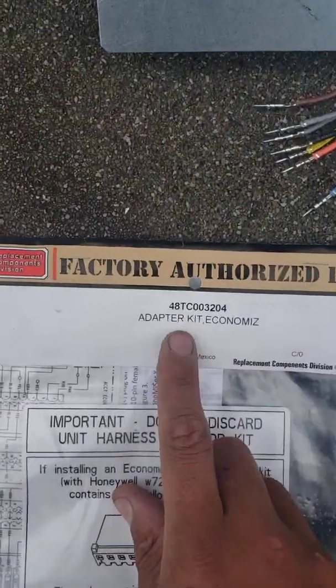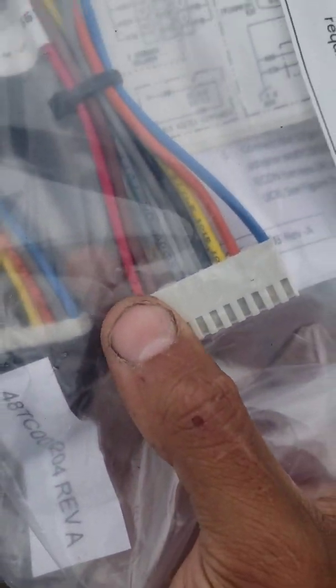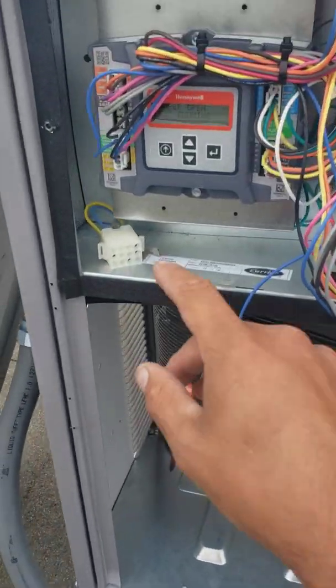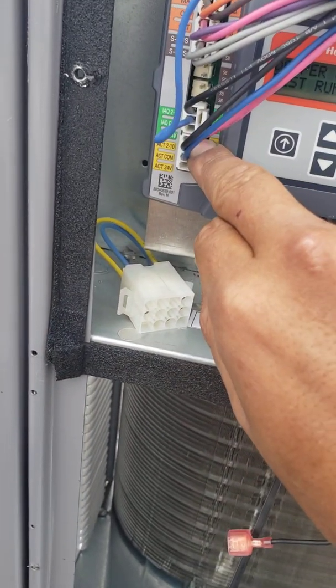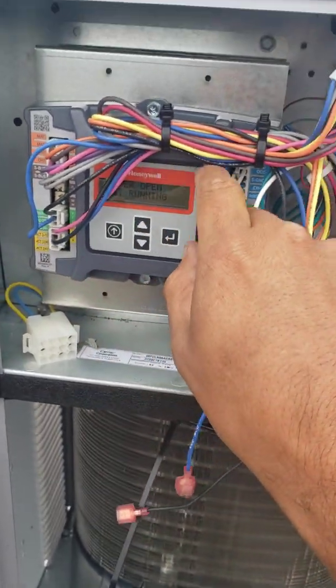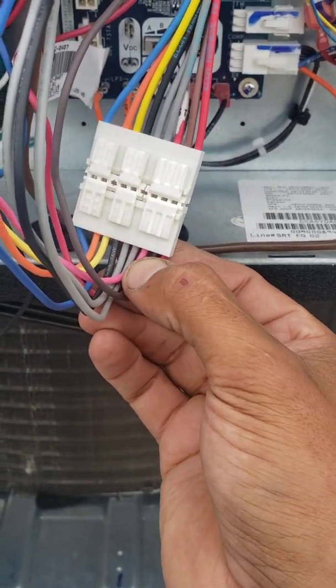And here's the kit. If you look right here, we have red, brown, black, gray, gray. Now if you look on here, our pink wire — 2 to 10 volts DC for our actuator — comes out of the pink wire. Right here: red, brown, pink.